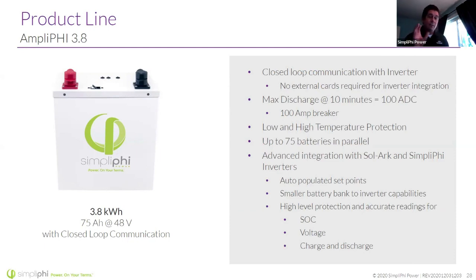Now, these integrations are going to give you some auto-populated set points, but not everything's going to be programmed for you. I like to say that there are customer expectation set points you still have to set. So, for example, depth of discharge. Do you want to do 80% depth of discharge so you get the maximum life out of those batteries? That's something you'd set. Or when your generator kicks in and for how long. Those would be some customer expectation set points that you would have to take care of. But a ton of set points are going to be programmed by the battery into the inverter, making for easier commissioning. And those include communications about state of charge, what kind of voltage ranges it wants, and max charge and discharge rates.